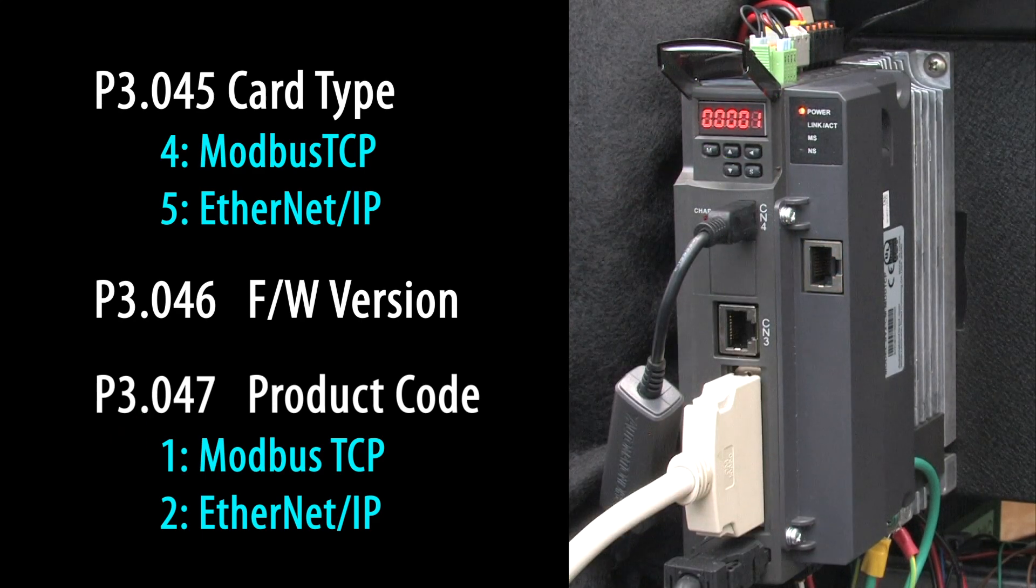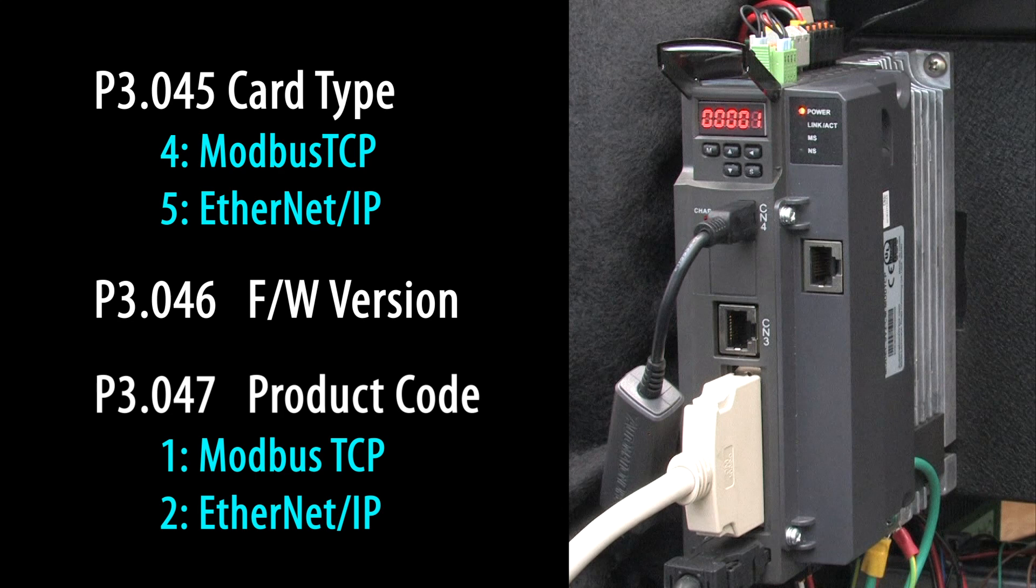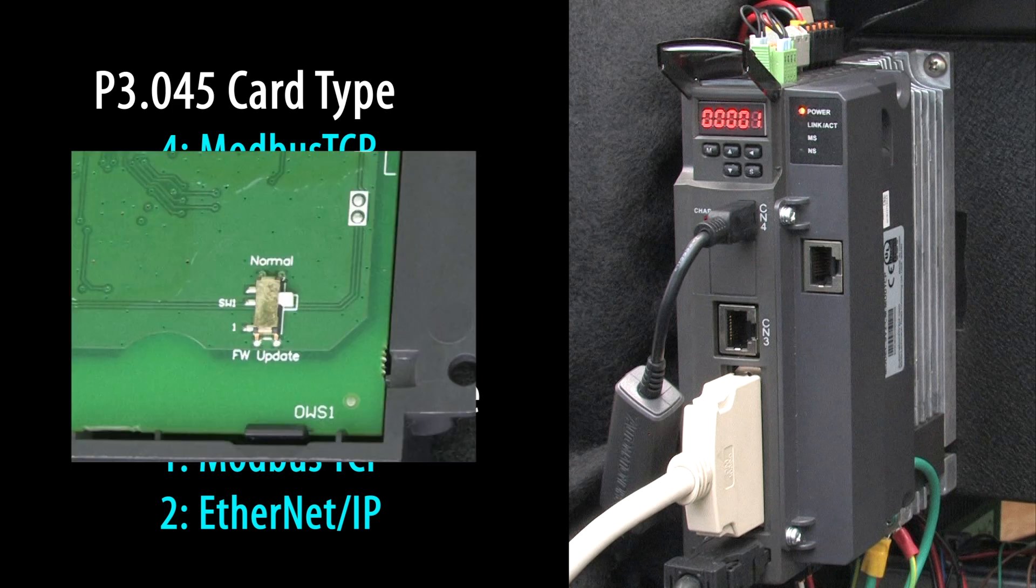If all of these are zero, then remove power from the drive, pull the card off by releasing the lower tab and lifting away, and double check that that little switch is all the way in the normal position. That will usually get it working.